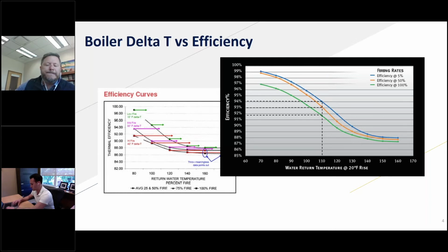So even though we're more efficient than, let's say, a standard boiler, or those boiler efficiencies that we were used to in the mid to high 80s, we're not quite as efficient as our most efficient point if we were to reduce that delta T. But when we look at the way that we've designed heating systems, a lot of times we go with a larger delta T, 20, 25, 30 degrees. There are some benefits in the system as well, but a lot of that was driven by the boiler efficiency.